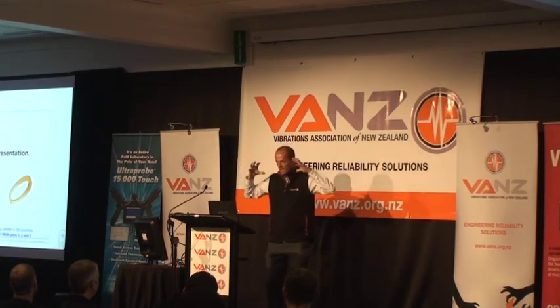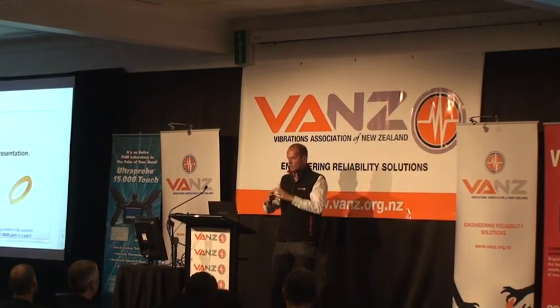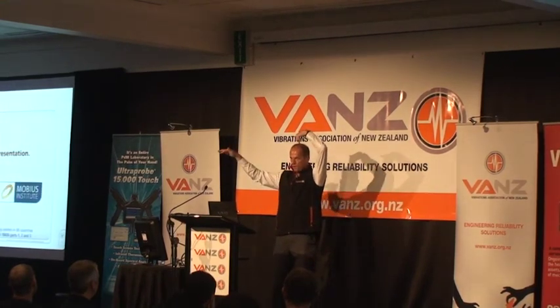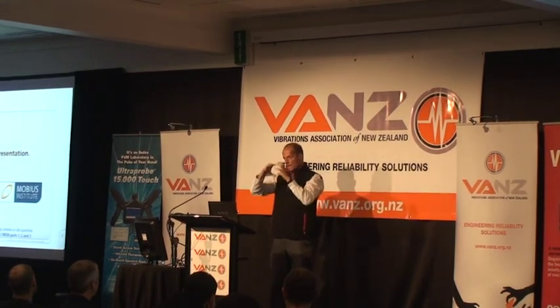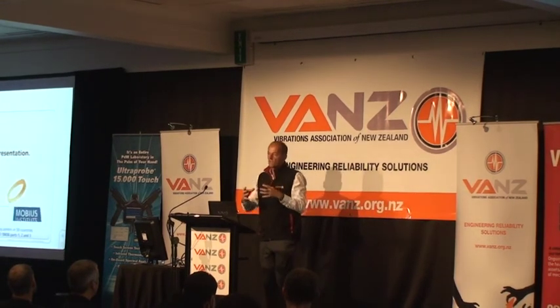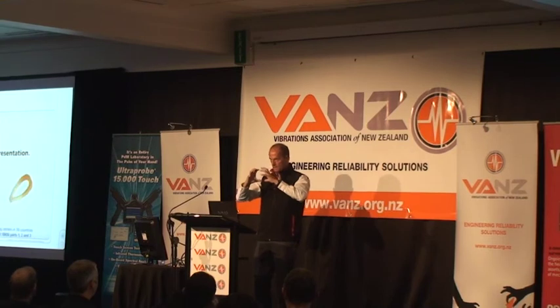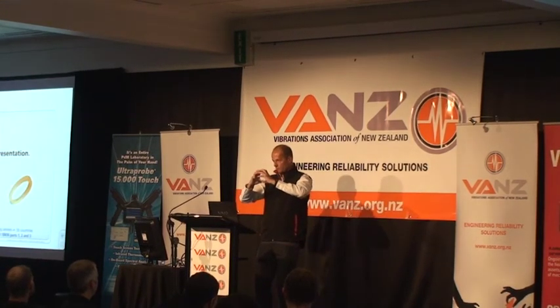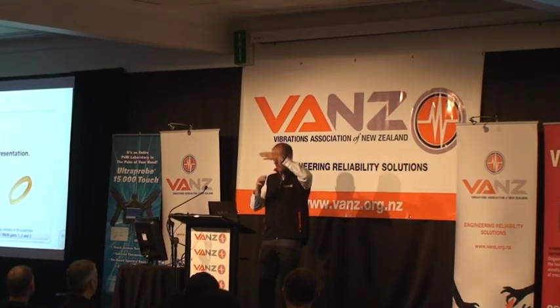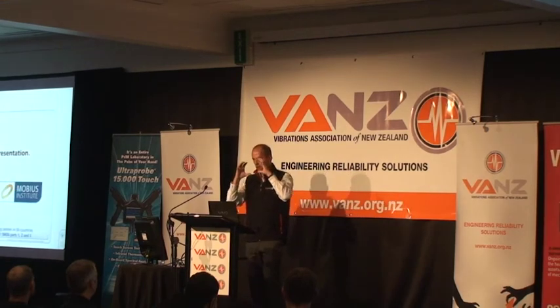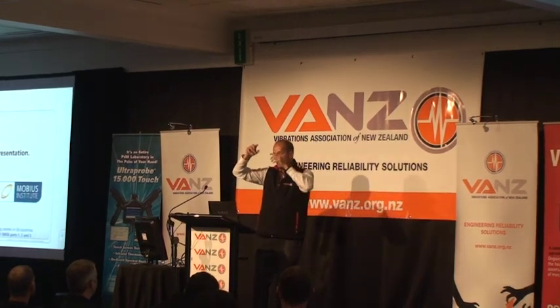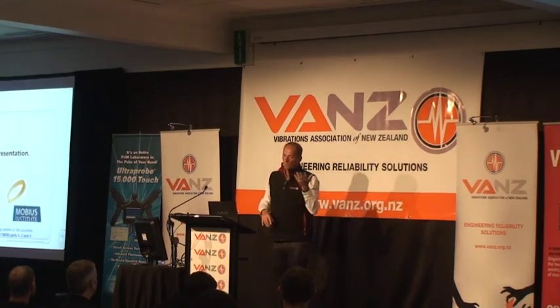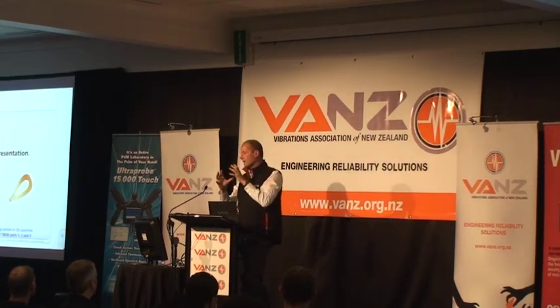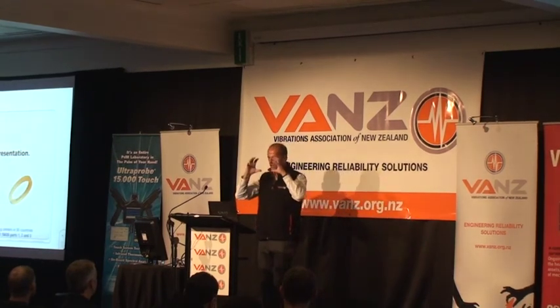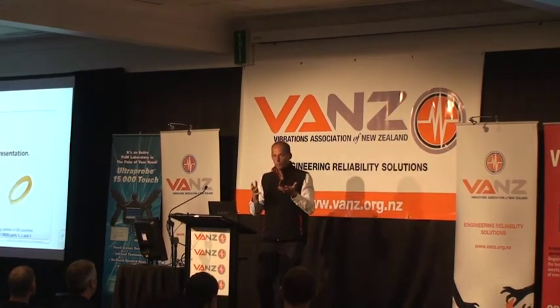So if we had a stationary bearing and the shaft moving inside, then the accelerometer signal would say no displacement, and the displacement signal would say yes, there is displacement. You can imagine a different situation where for some reason the shaft is actually spinning, let's just call it without motion, and the bearing cap for some reason is moving. Well, the proximity probe is going to see the relative movement between the probe, the housing and the shaft, but the accelerometer is going to see the same thing. It's seeing that motion. So people will often use the accelerometer as well as proximity probes to zero out what is the shaft doing relative to ground. But they will give you different results.